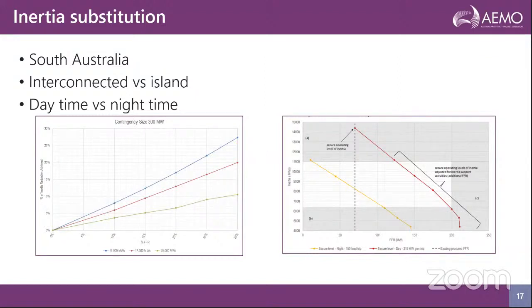if we have 120 megawatt of FFR available in the grid, then the inertia required to meet the system security is about 11,000 megawatt second. On the other hand, if we have 200 megawatt of FFR available, that inertia requirement will reduce from 11,000 to 6,200 megawatt second of inertia, and it will still achieve similar outcome. Okay, so that shows that you can substitute some portion of your inertia by procuring fast frequency response from battery, and that is particularly used for South Australian system.